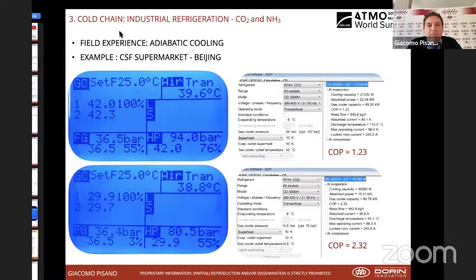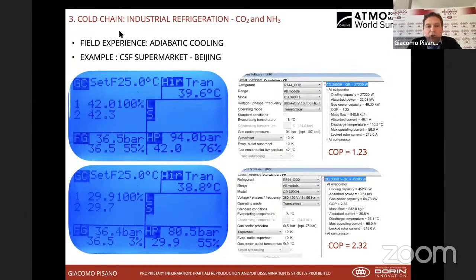If we put these numbers into a selection software, you can see that the COP without the adiabatic cooler engaged is 1.23, while the same compressor working in the operating condition registered here will bring a COP of 2.32. So definitely, when possible and when it makes sense, adiabatic cooling brings a lot of COP boost when talking about CO2 transcritical.